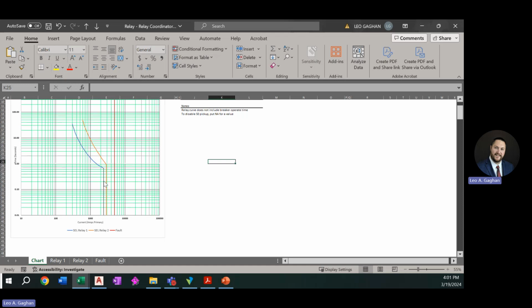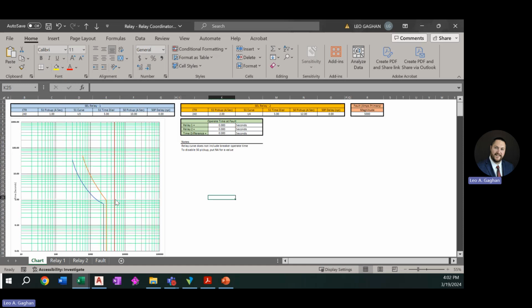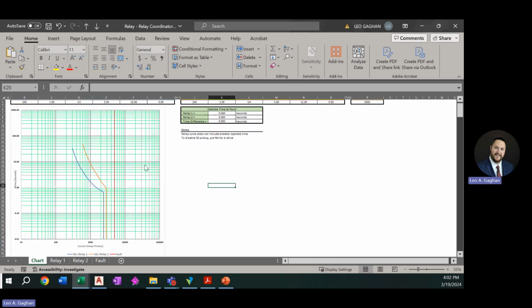That's this vertical portion of the curve. As I increase it, it'll move it to the right. With the fault current to the right of the instantaneous element, that means it will operate instantaneously, which is the case right now, right? The fault current is to the right of both of our instantaneouses. We can see both of our relays are going to operate instantaneously, and there's going to be no time difference.